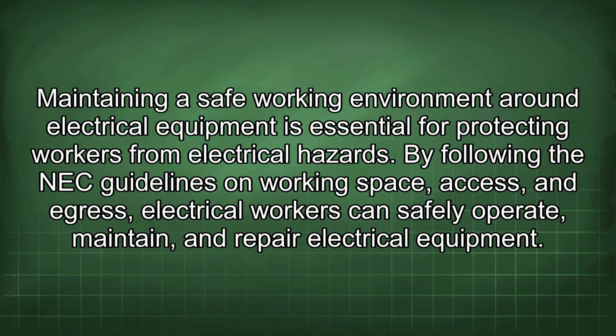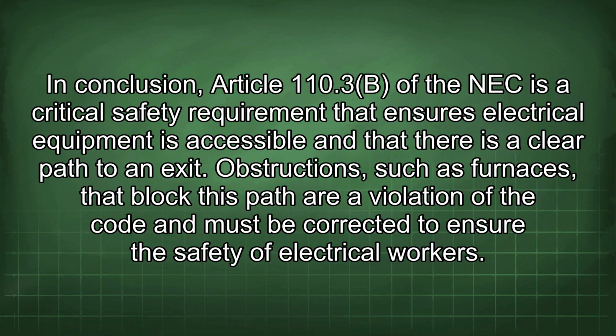Maintaining a safe working environment around electrical equipment is essential for protecting workers from electrical hazards. By following the NEC guidelines on working space, access, and egress, electrical workers can safely operate, maintain, and repair electrical equipment. In conclusion, Article 110.3(B) of the NEC is a critical safety requirement that ensures electrical equipment is accessible and that there is a clear path to an exit. Obstructions, such as furnaces, that block this path are a violation of the code and must be corrected to ensure the safety of electrical workers.